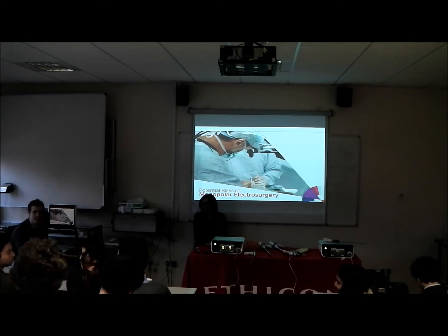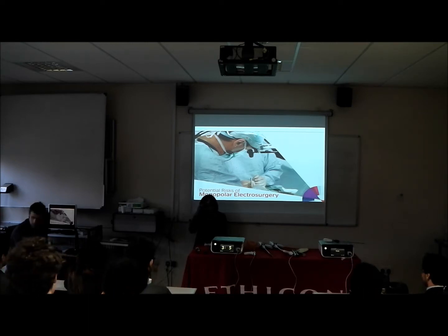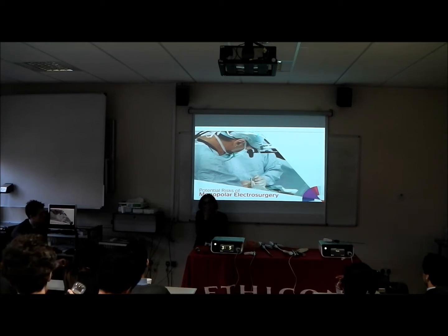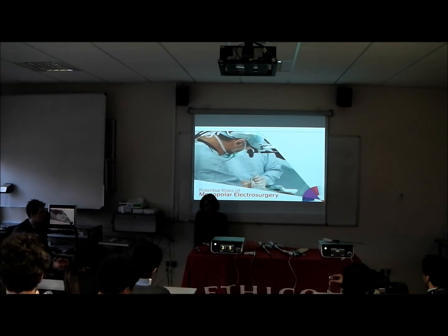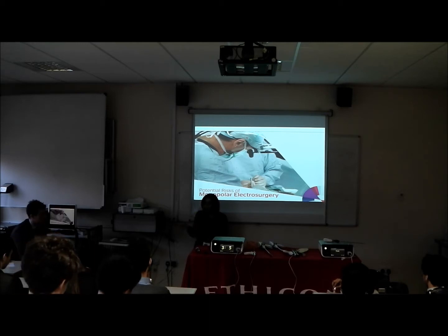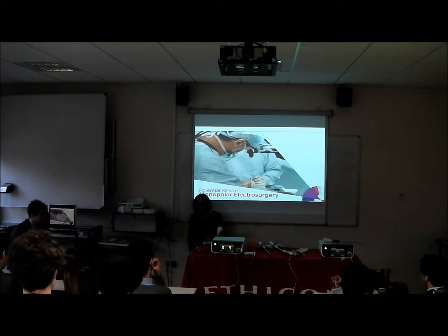There's something wrong with the computer controlling it. The patient might get killed. What you're trying to say in principle is that if there's anything wrong with the generator or the electric current, what can happen? If it stops working, then you can't do the surgery. I suppose that is one of the things that can happen. But usually these generators are really good. If they stop working, they don't cause harm to the patient. If there's anything wrong with the circuit, they will automatically switch off as a safety. If the patient return electrode is not applied properly, they will not run, and you will not be able to use it.